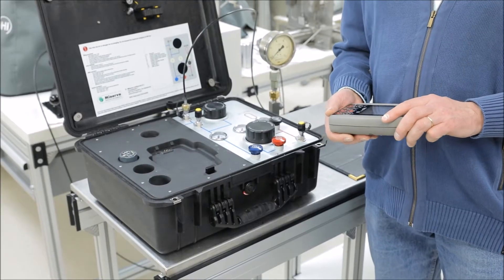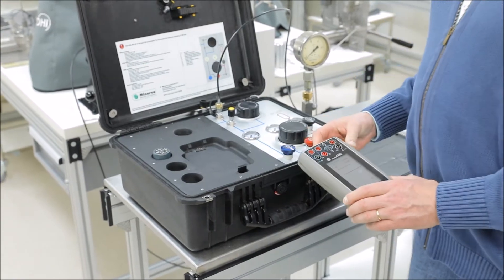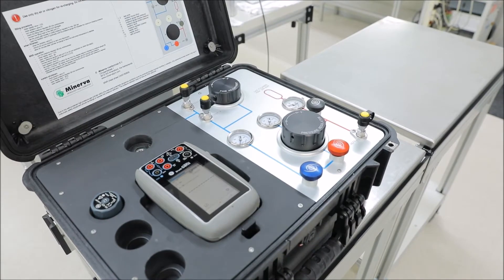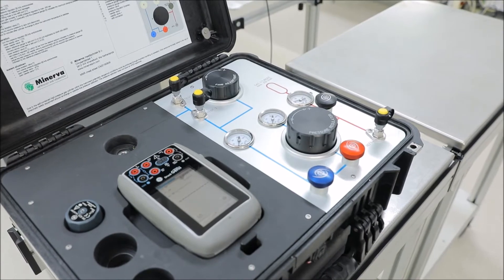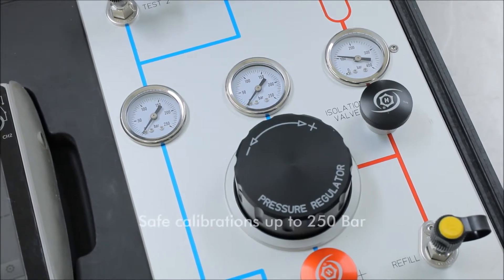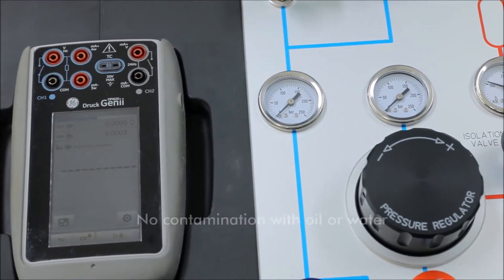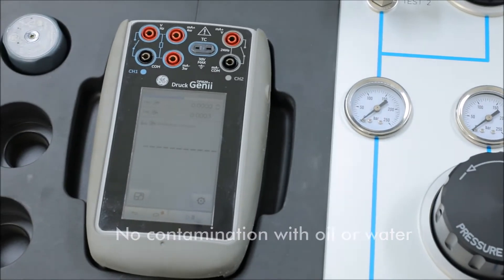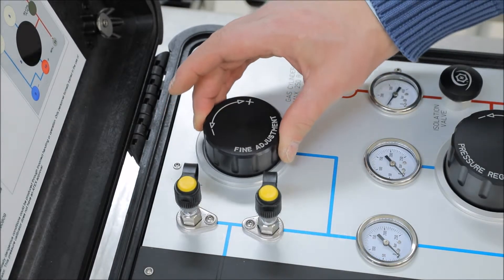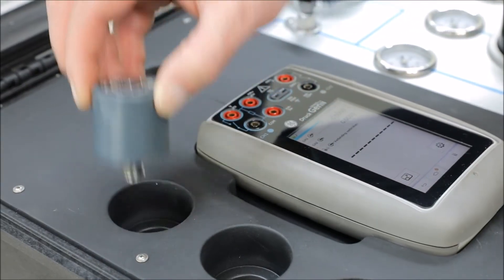The Minerva Portable High Pressure Case can accommodate one GE Druck DPI620G, and we click it in like this. This case offers improved efficiency to quickly and safely perform clean high pressure calibrations at your location. It enables you to perform safe pneumatic calibrations up to a maximum pressure of 250 bars, not contaminate the device under test with oil or water, perform precise test pressure control using a pressure balanced volume adjuster, eliminate trouble with trapped air in a hydraulic system, and exchange calibrator pressure modules quickly and easily.